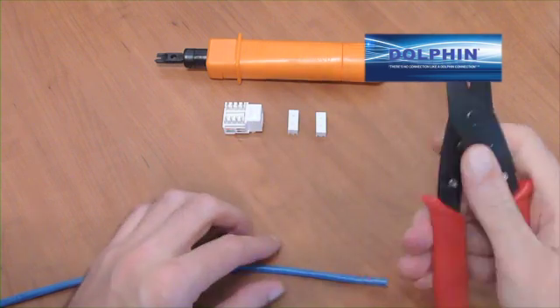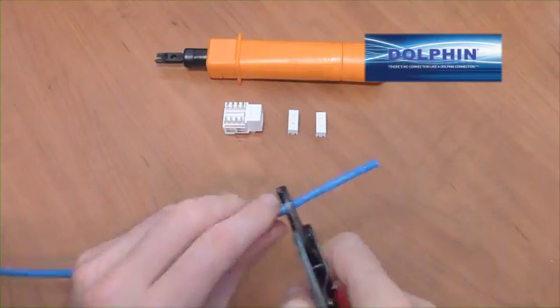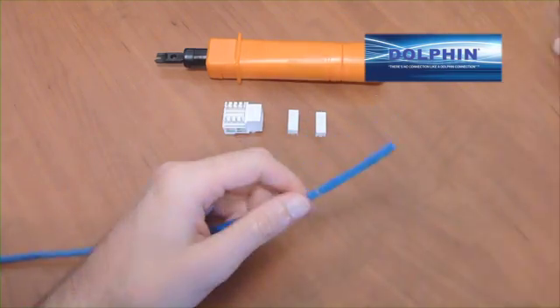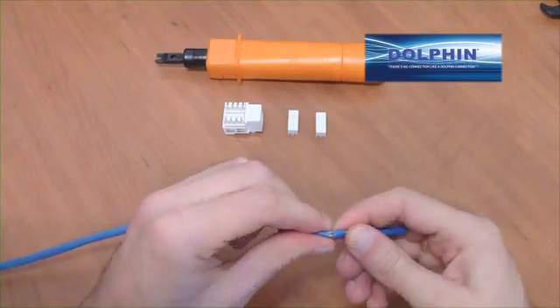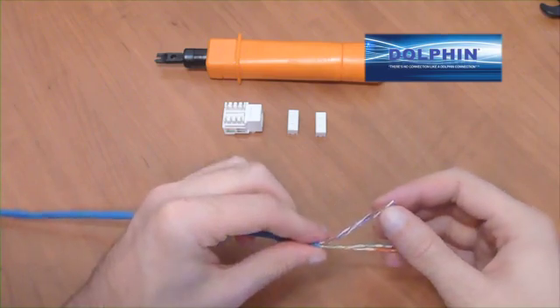Beginning at the raw end of the cable, strip a small length of the outer sheathing to expose the twisted pairs, central wire separator, also known as the spline, and the pull string. Once exposed, use pull string to expose 2-3 inches of length of the fresh twisted pairs to avoid using any wire that may have been nicked during the stripping.